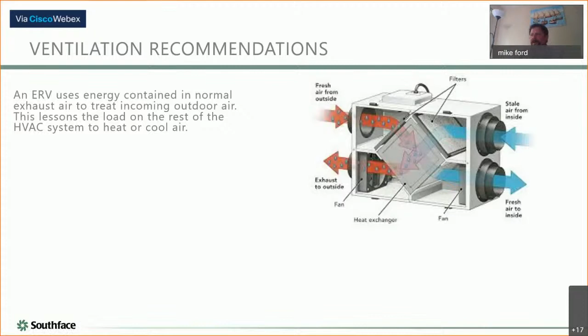You can do this with cold air or hot air, and they also have the effect of dehumidifying in summer, because that dry air going out crosses with the humid air coming in, and they help humidify in winter, which is what you want. So that's recommended for homeowners as part of a well-rounded ventilation system, and in commercial as well. It's required by the energy code in certain commercial buildings if they're moving a certain amount of air, a pretty big amount. So you'll be required by law to have it in a big building moving a lot of air, but we recommend it regardless.